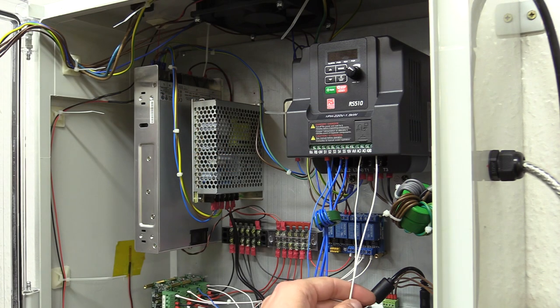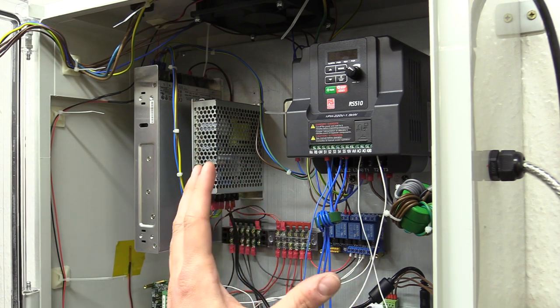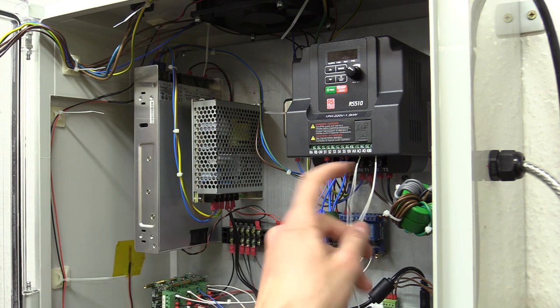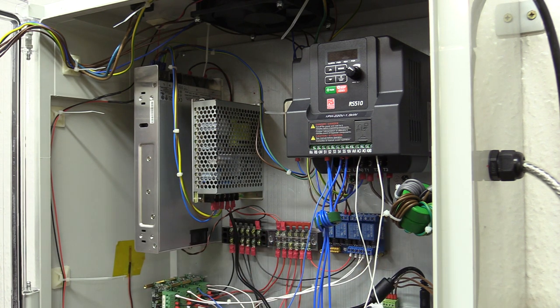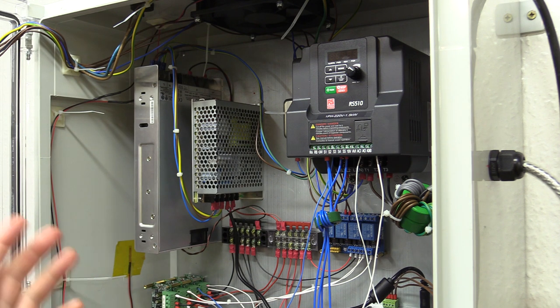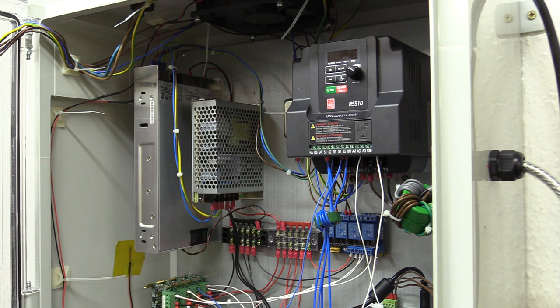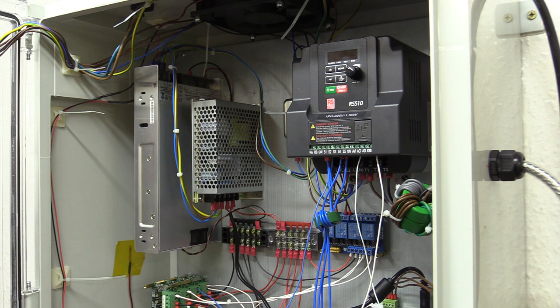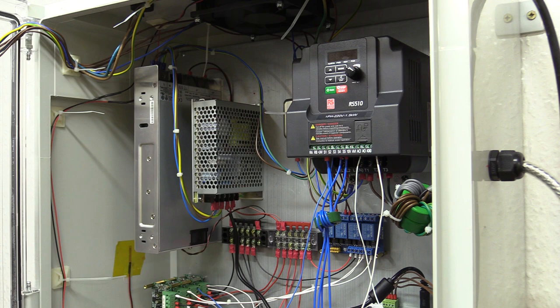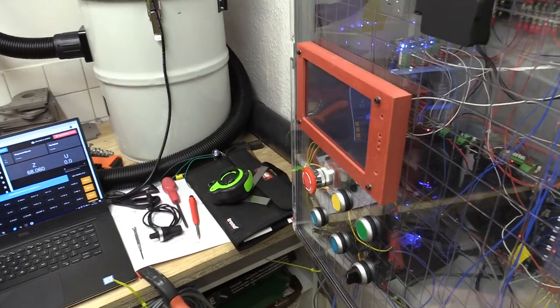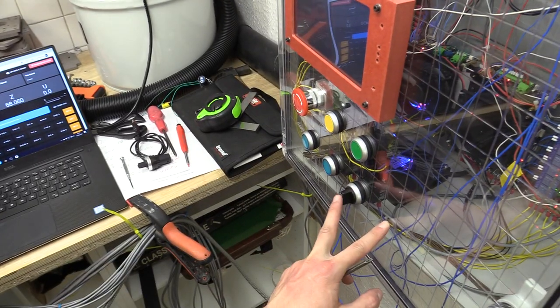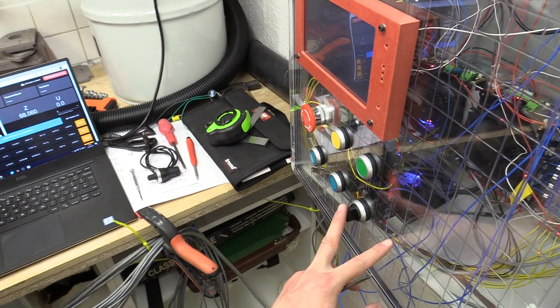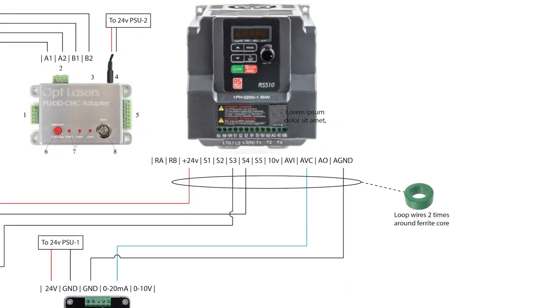To control the speed, the signal and ground from the PWM to analogue converter is wired into the AVI and analogue ground on the VFD. And I've also been able to select between two different speed inputs so I can go from the controller and then by flicking a switch I could then use the potentiometer on the actual VFD.